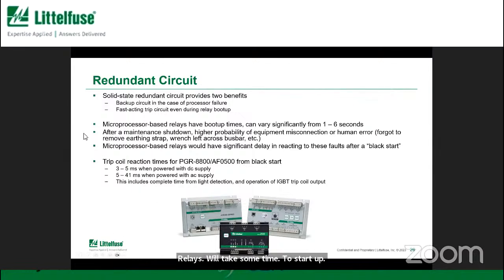I don't mean just these relays, but all microprocessor-based relays will take some time to start up. But one of the times you might be most likely to have an arc flash is immediately on power up, because maybe you've been doing maintenance and you had everything turned off, which is great, did the maintenance, and you're going to turn the system on, but maybe somebody forgot the grounding or the earthing straps, and so there's a short on the bus, and you turn on the equipment right into an arc flash. So if your arc flash relay is going to take 2 seconds or 1 second to start up, you could have an arc flash for 1 second, which could be devastating. Like that could be complete destruction of the equipment.